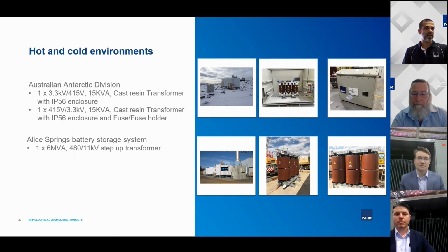and designed to still cater for the full load, which in this case was 6 MVA, which is quite a large transformer in general. So the transformer had to be derated, or rated for a higher ambient temperature. I think in this case it was 50 degrees. And also there was a fan arrangement, which was an N+1 fail-safe arrangement to cater for the airflow requirements for this transformer.